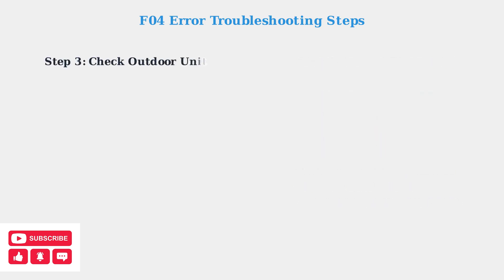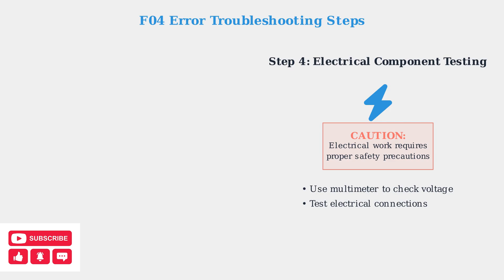If basic checks don't resolve the issue, examine your outdoor unit. The F04 error may originate from problems with the condenser, electrical connections, or restricted airflow around the outdoor equipment. For advanced troubleshooting, use a multimeter to check voltage and test electrical components. However, this requires electrical knowledge and proper safety precautions.